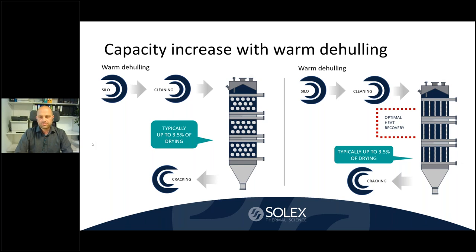Bypassing the jet dryer benefits energy managers, since indirect conditioning is always more efficient than conditioning with air in direct contact with the seeds. It benefits maintenance managers through less rotary equipment such as huge fans for conditioning and fluidization of the product, no need for very large air operators, and generally lower emissions since the plate technology needs only the amount of air required for moisture evacuation, not for conditioning itself. For plants already on warm dehulling looking to increase capacity, existing tube conditioners without integrated heat recovery and designed for a certain production rate can become a major bottleneck. The plate technology can provide vital debottlenecking by providing twice as much heat transfer area within the existing space, or the extra space can be used for waste heat recovery or for a smaller design still meeting new production rate requirements.